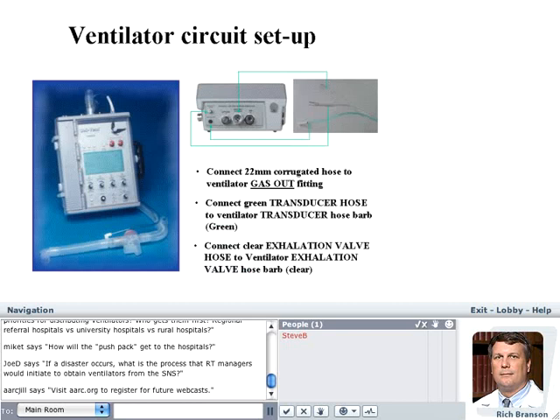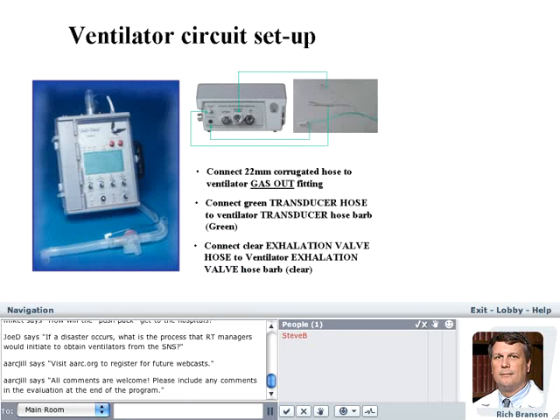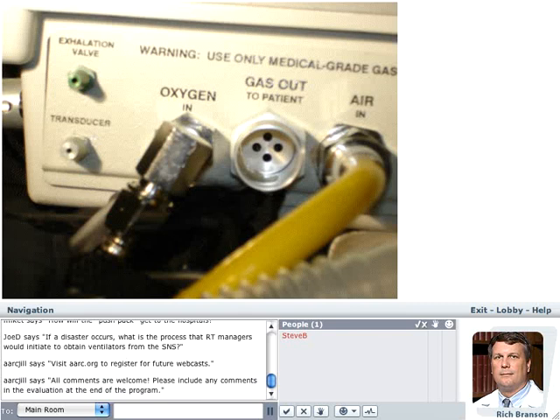And the ventilator recognizes when it gets 50 psi air and shuts off the compressor automatically, which significantly lengthens the battery life. And this is just a picture up close. So you see the exhalation valve and the transducer are color-coded. And this is one where we have high pressure oxygen and high pressure air connected to the ventilator.